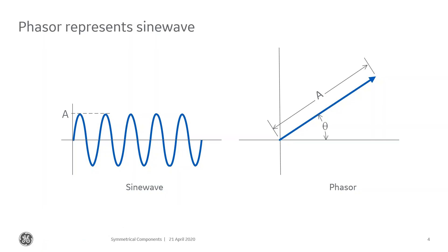So let's talk about what a phasor is. When I set an overcurrent relay — an overcurrent element in a microprocessor-based relay — I usually set a pickup value. In our relays, that's in per unit of CT. So if it's a 200:5 CT and I set that at one, that means it's picking up at 200 amps. But what really is 200 amps? I kind of think of that as the RMS quantity, but it could be the phasor.